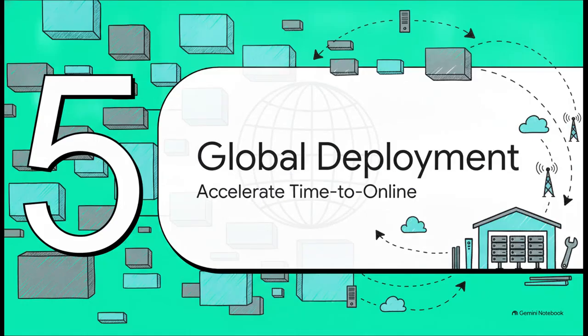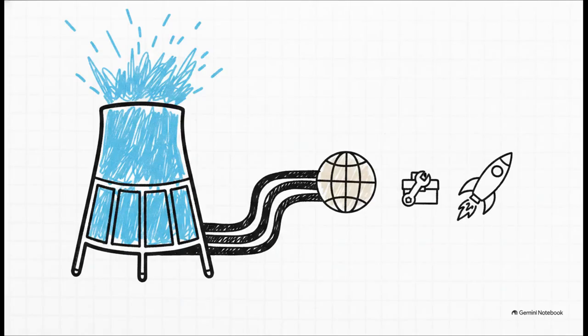And finally, Section 5, Global Deployment and Support. So you have the blocks, but how do you actually build the physical facility? The building block philosophy extends way beyond the server racks to the site infrastructure itself. We're talking about massive water cooling towers that can support capacities anywhere from 1 megawatt all the way up to 50 megawatts or more. It includes complete site-scale cabling design to significantly reduce your material costs and labor.